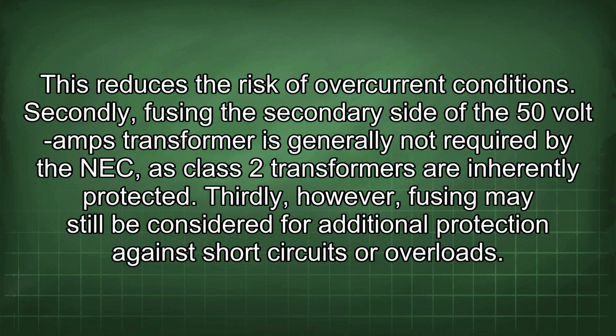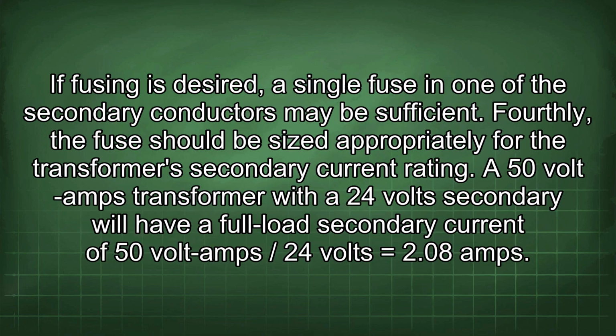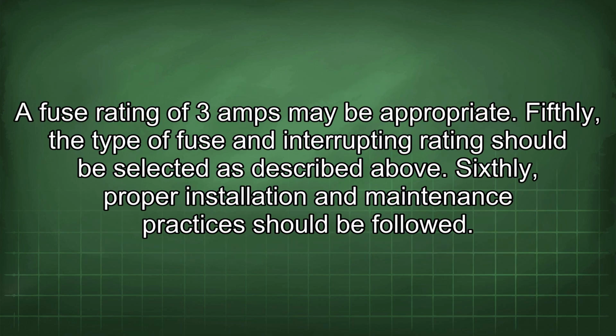Thirdly, however, fusing may still be considered for additional protection against short circuits or overloads. If fusing is desired, a single fuse in one of the secondary conductors may be sufficient. Fourthly, the fuse should be sized appropriately for the transformer's secondary current rating. A 50 volt-amp transformer with a 24 volt secondary will have a full load secondary current of 50 volt-amps / 24 volts equals 2.08 amps. A fuse rating of 3 amps may be appropriate. Fifthly, the type of fuse and interrupting rating should be selected as described above. Sixthly, proper installation and maintenance practices should be followed.